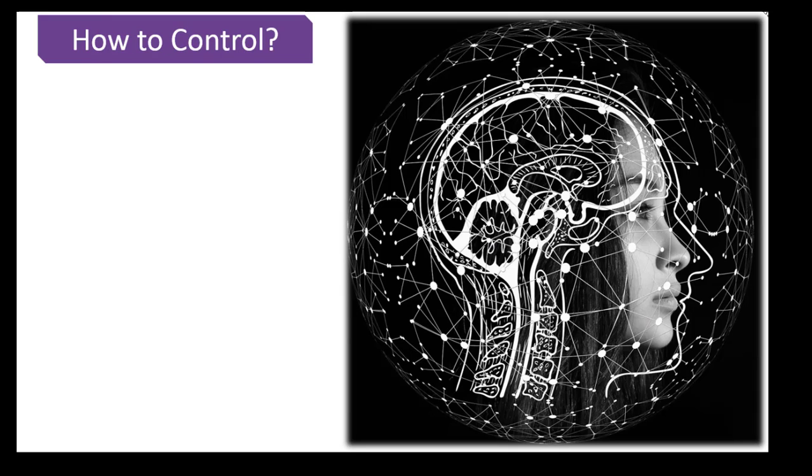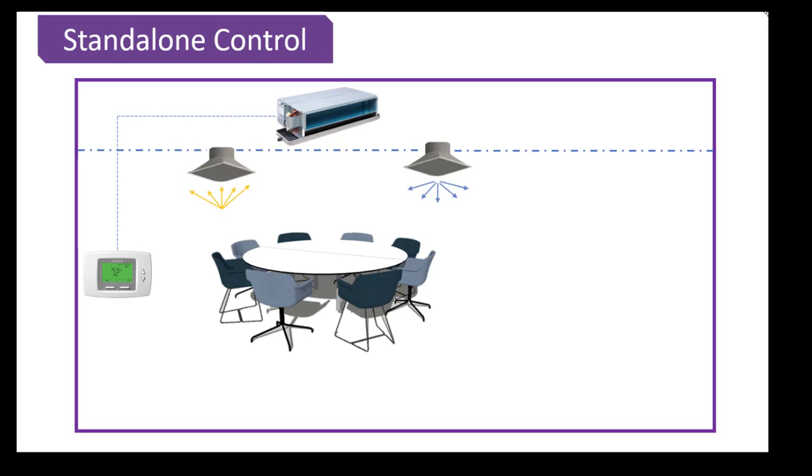Now let's discuss how to control an FCU. There are two ways to control an FCU. First way is to use a local thermostat for standalone control and then other way is to use a DDC controller. Now let's have a look at both of them in details. First of all for the standalone control we are using a local thermostat which is not connected to the BMS so we will not be able to control or monitor this type of FCU from the BMS.